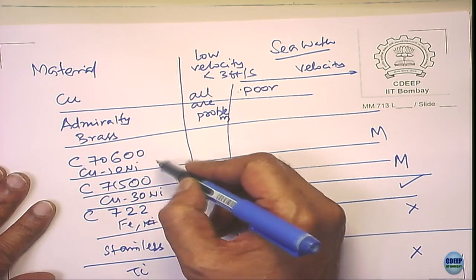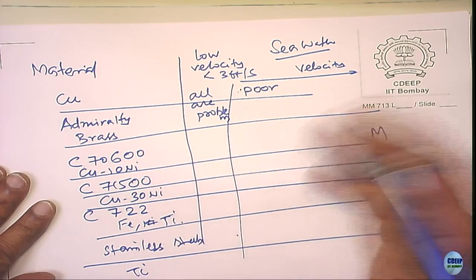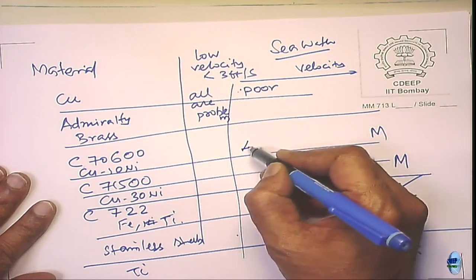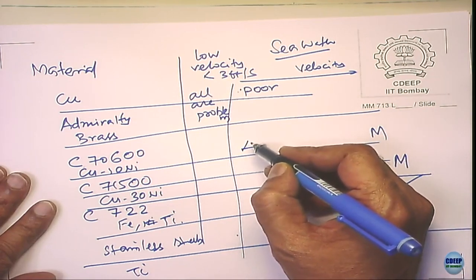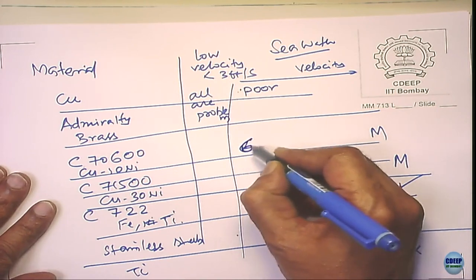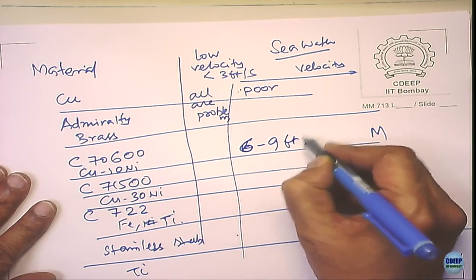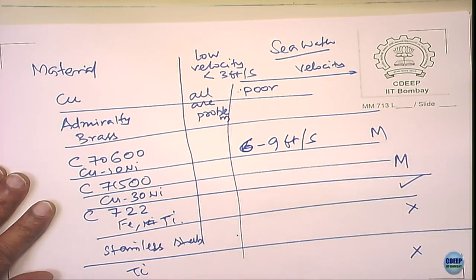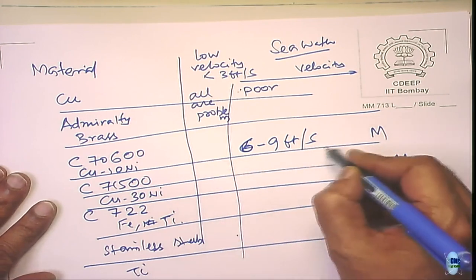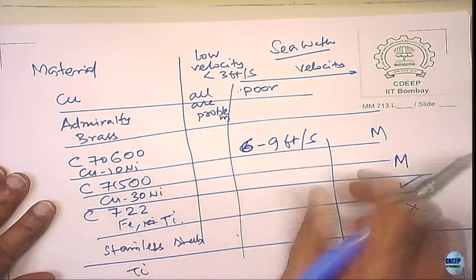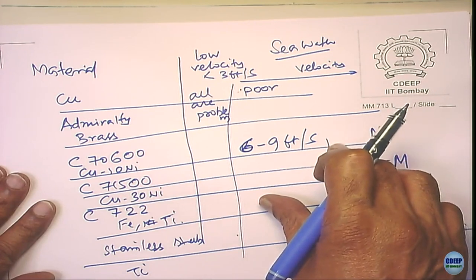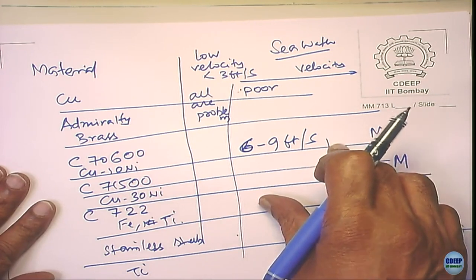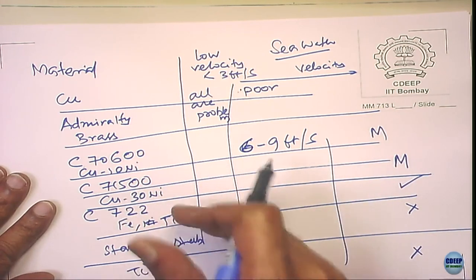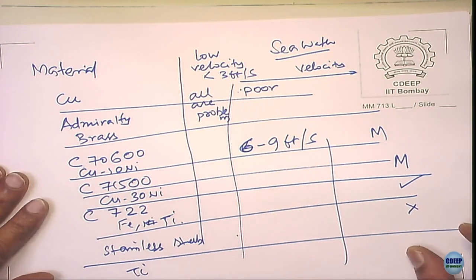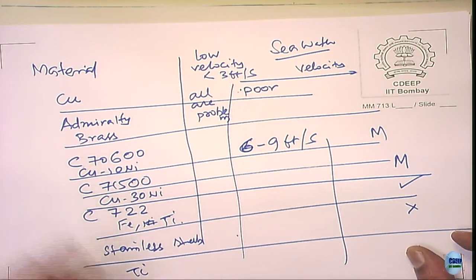So all these copper based alloys, the velocity is maybe around about, I think probably about, you can go up to maybe about 6 to 9 feet per second velocity that you can go for it. This is higher, so beyond that, the copper based alloys would have a problem. So higher velocity means stainless steels and titanium alloys - these are the ways that you can use it. But titanium alloys can be used, while the stainless steels of all categories cannot be used in seawater application, right? There is some problem. What is the problem there?